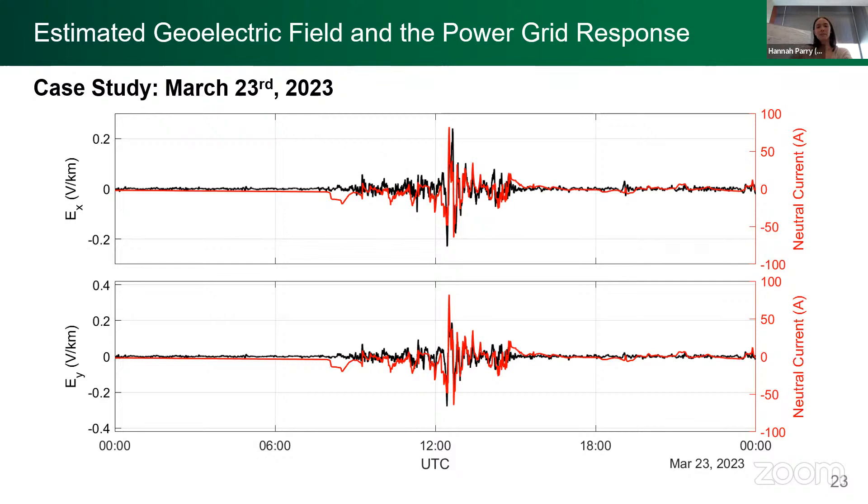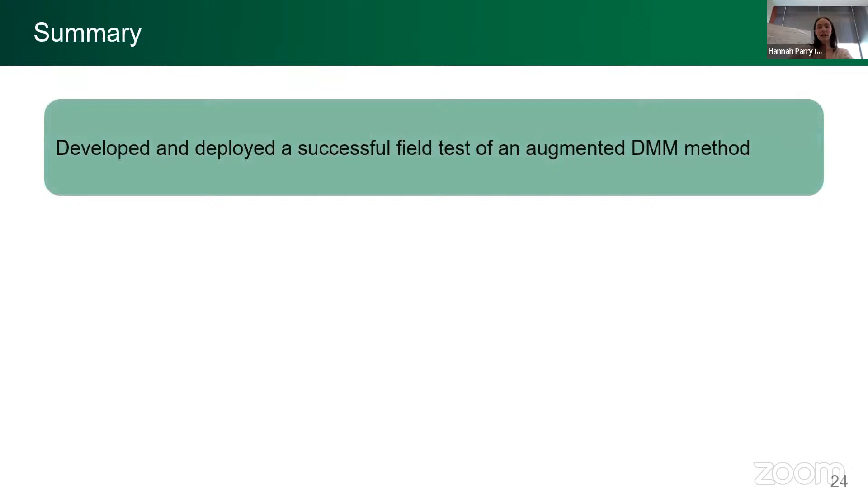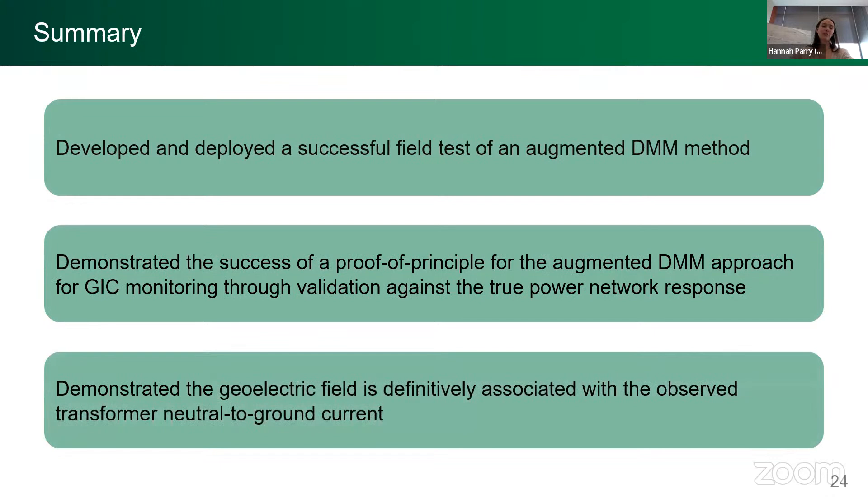Like I mentioned, the geoelectric field can be calculated through a convolution of the horizontal GMD components, so your magnetic field, horizontal magnetic field components, and the transfer function Z over mu naught. Now, Z here is just the frequency-dependent tensor, which describes the ability of Earth's crust to conduct current. And it's defined by the ratio of measured E and B from magnetotelluric surveys. So it's just this middle equation that does all the action. So we're going to calculate geoelectric field at Meanook. And since Meanook is only approximately 33 kilometers away from Ellerslie and about 50 kilometers from the DMM location, we're going to assume that the geoelectric field at this location is representative of the geoelectric field across the entire power line segment. And so we're going to directly compare the geoelectric field to the GIC at Ellerslie. And that's what's plotted here for that first event, October 12th. And as you can see, large responses in the geoelectric field elements are well characterized by the neutral current elements. And again, this is the second event from last month, March 23rd. We're demonstrating here, again, EX and EY compared to the neutral current. And this is really powerful because it's drawing a direct link between the driver and the GIC response in the network. And it's showing that GIC is flowing through the Alberta network during even moderate geomagnetic storms and validates that the augmented DMM approach is indeed measuring excess DC current in the power system, ultimately caused by space weather.